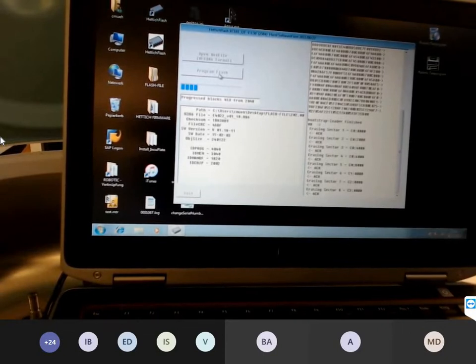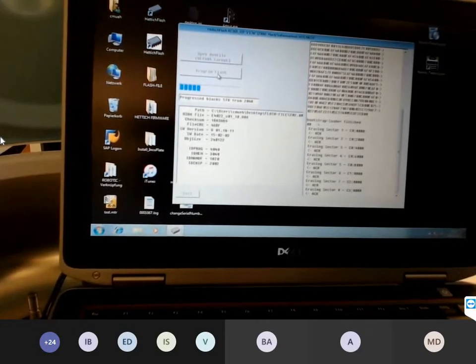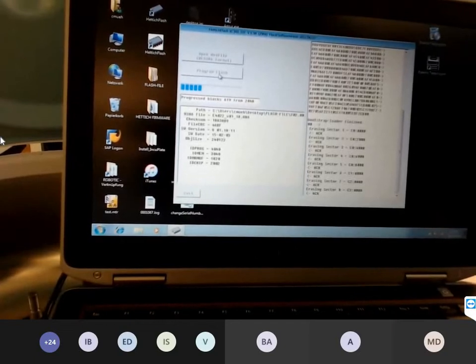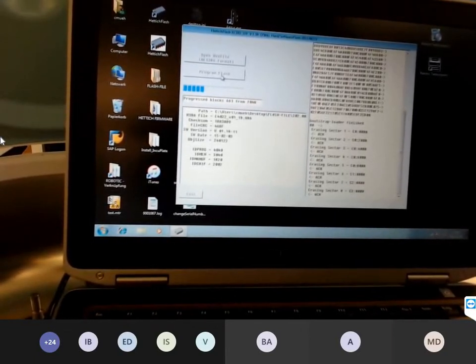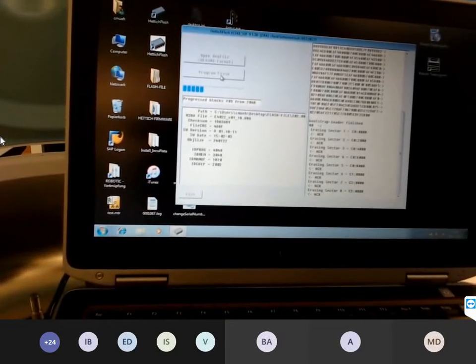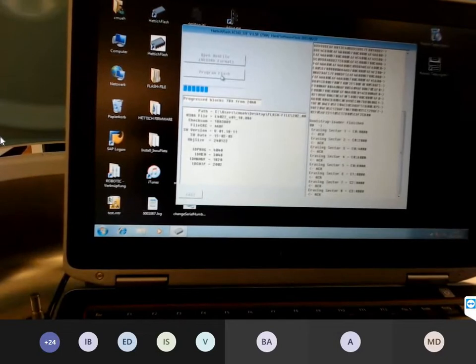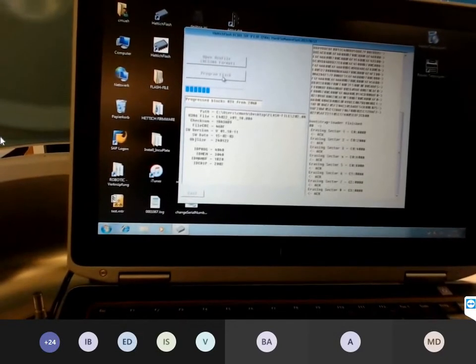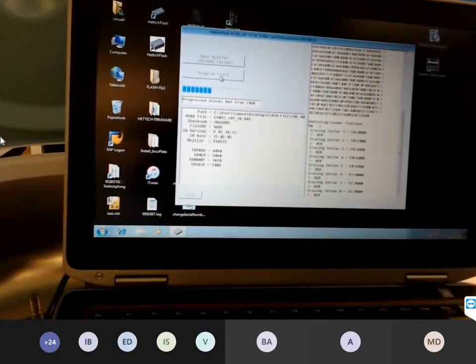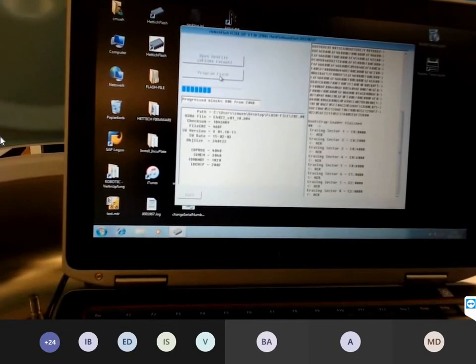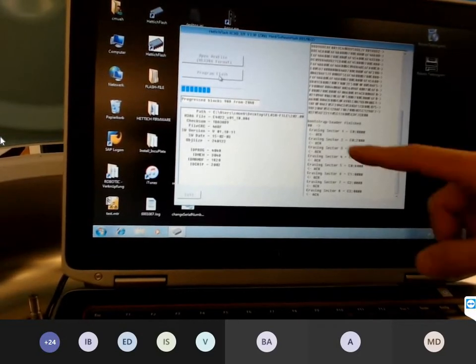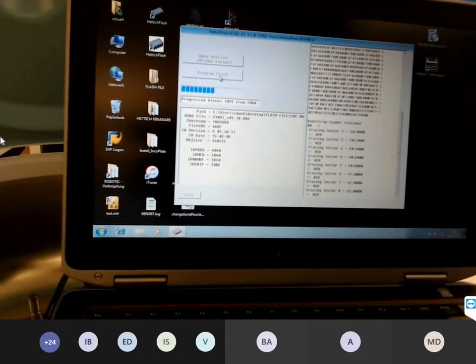I repeat, you have to flash the software update in case of accessories. If you need new accessories like the latest rotor, you have to flash it. You can flash the Rotina, or you can flash all centrifuges with the C control board. It's very important. You cannot flash the universal or the micro. You can only flash all centrifuges with the C control board. Now we have to wait. We have 2048 digits as a hex code.